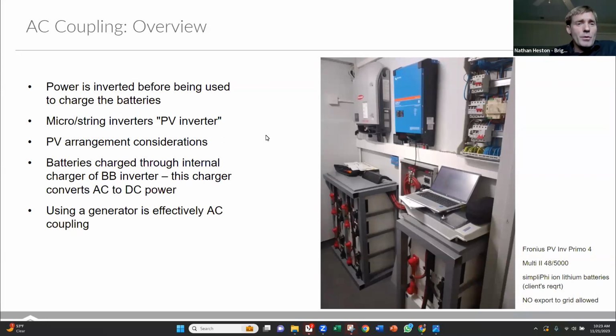It's important to consider the PV arrangement. So with AC coupled solar systems, you have to consider where that power is coming from and going to. In the case of this equipment, there are some limitations as well. And if you are connected to the grid in a grid down situation, you have to make sure that your equipment is capable of frequency shifting and turning off those microinverters so that they're not trying to overpower equipment. Batteries are charged through the internal charger of the BB. That stands for battery bank inverter. This charger converts the AC to the DC to run those charge cycles on the batteries. You can also use a generator for AC coupling.